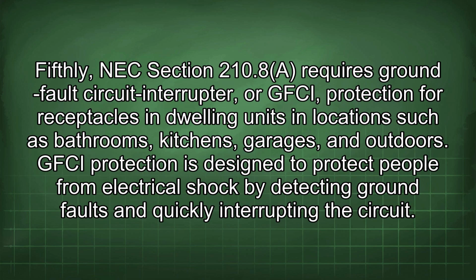Fifthly, NEC Section 210.8 requires ground fault circuit interrupter, or GFCI, protection for receptacles in dwelling units in locations such as bathrooms, kitchens, garages, and outdoors. GFCI protection is designed to protect people from electrical shock by detecting ground faults and quickly interrupting the circuit.